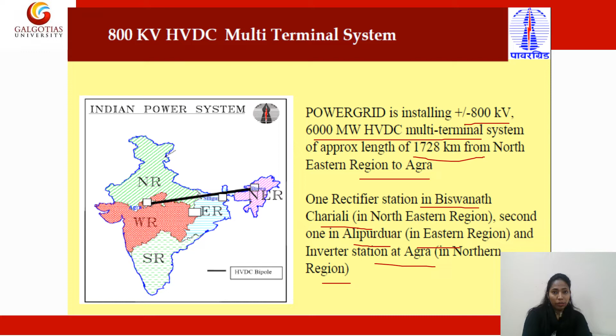Here Power Grid is installing a plus minus 800 kV, 6000 megawatt HVDC multi-terminal system of approximately 1728 km length from the northeastern region to Agra. One rectifier station is in Biswanath Chariali in the northeastern region, the second one is Alipurdwar in the eastern region, and the inverter station is at Agra in the northern region. These three stations are interconnected, and this is the first project in India which is multi-terminal and working on an 800 kV HVDC system.